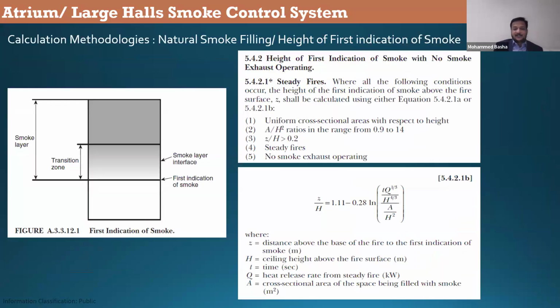Now, calculation methodologies. I do not want to take you into full calculation, but I want to explain the way to calculate. The first methodology of smoke control system I was explaining to you is natural smoke filling. The images and formulas you are seeing in the slides are taken from NFPA 92. It is not my own literature. As you can see in the left side figure, this is from section 5.4.2 of NFPA 92, which talks about height of first indication of smoke with no smoke exhaust operating.